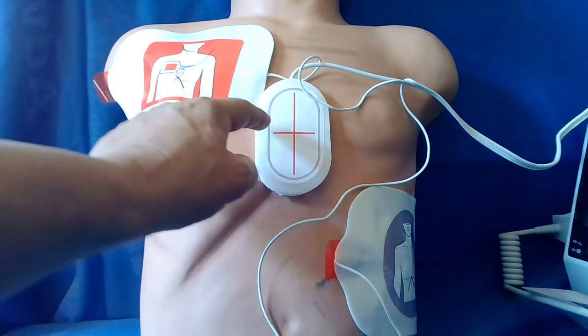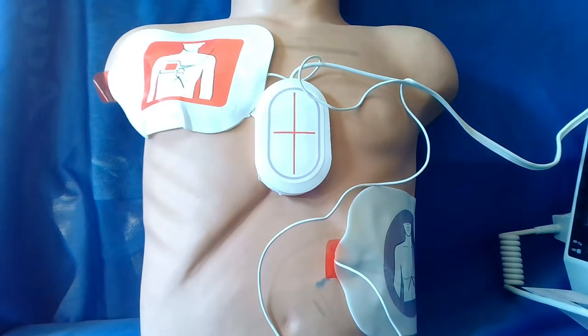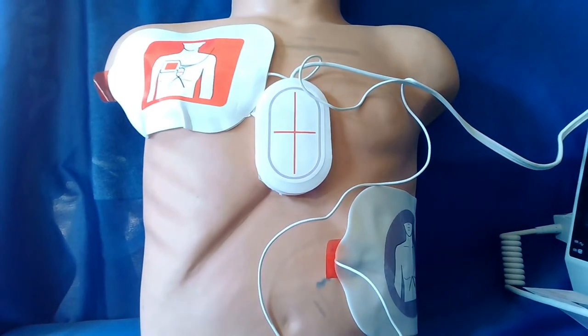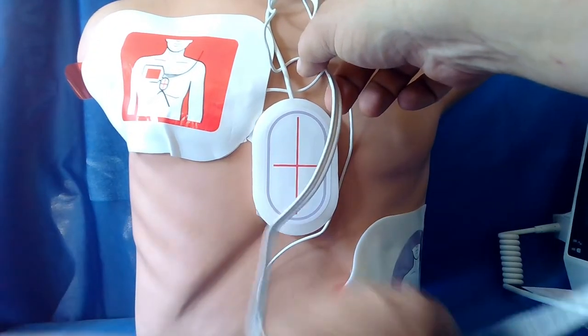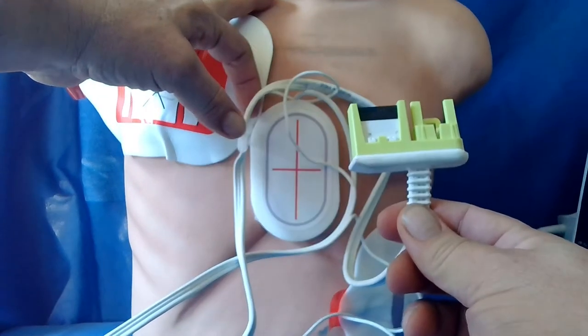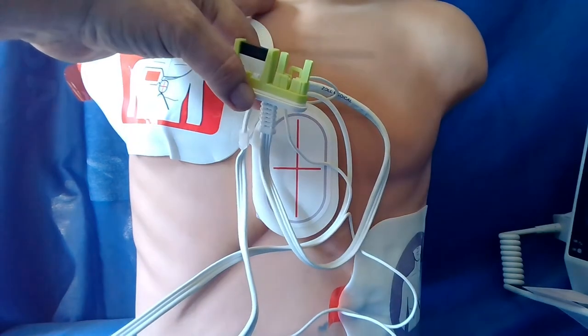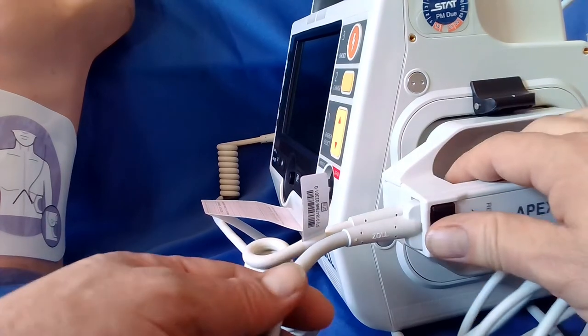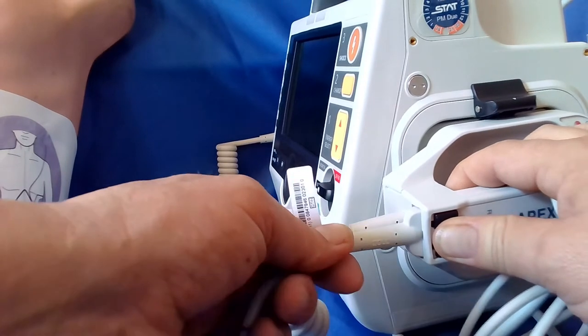And on the puck you see this red line or red cross, which is in line with the midline of the patient and in line with the nipple line of the patient. When you place that, this pad will be placed and set in the correct position as and when needed. Our cable then gets connected to a multifunction cable, which is removed from the paddles. So remember, when we did our checks, we wanted to make sure this was clicked in properly.